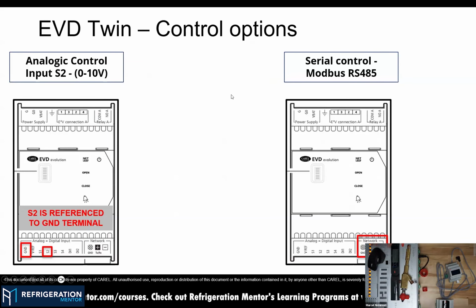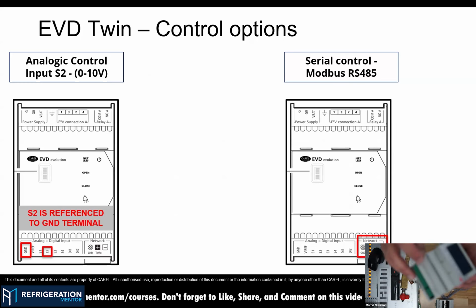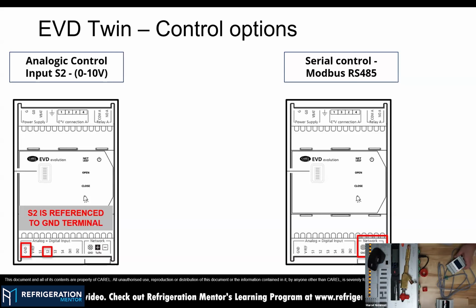And the ways of controlling the ejector. We have pretty much 2 main ways to control it. The first one is with a 0 to 10 volt signal. We can see here that I have the terminals indicated. So when it's 0 to 10 volt and you see a wire going from GND and S2, you can identify this as 0 to 10 volt control. With that, you can come with your meter and check the voltage that you have there. So it will be easier for you to troubleshoot if it's a 0 to 10 volt signal.